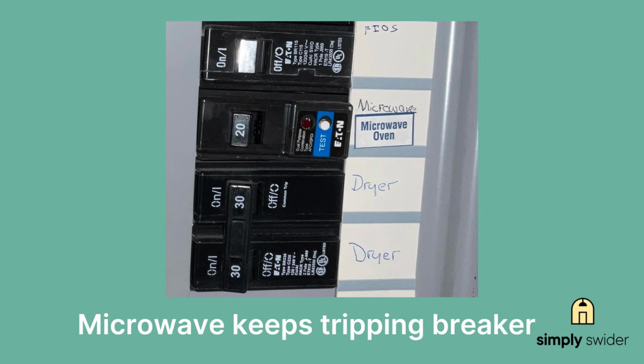Here's your action plan. Start by checking if other appliances are running on the same circuit. That's a 2-minute test that solves 30% of these problems. Next, listen to when the breaker trips. If it's when opening or closing the door, you're looking at door switches. Only move to high voltage components if those first 2 checks come up empty. Follow this sequence and you'll solve most breaker tripping issues in under an hour.